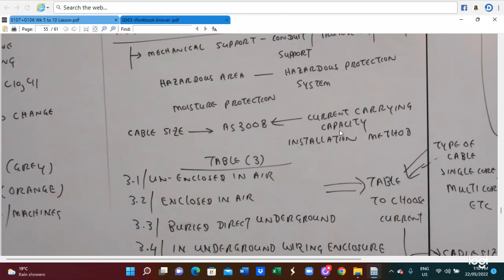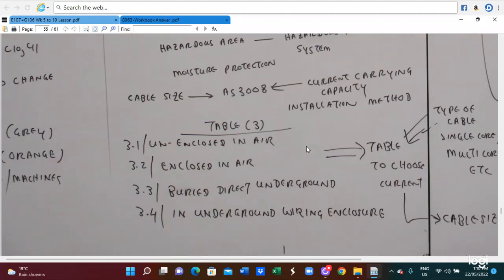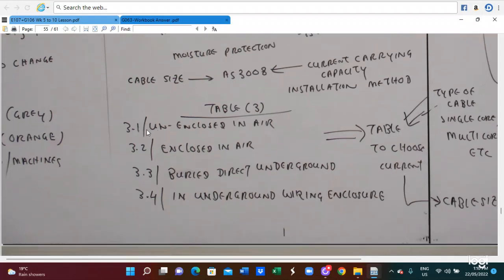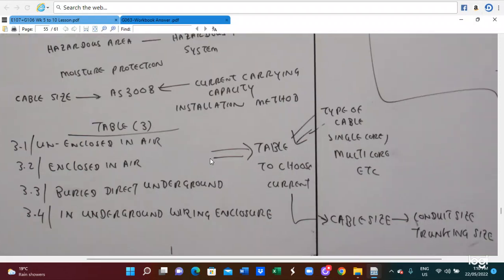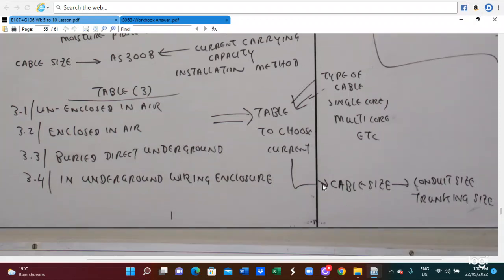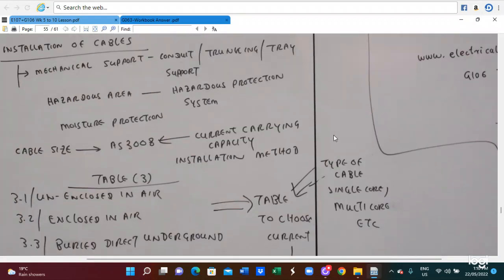This is the current carrying capacity and the installation method. So for cable, 3x1 is un-enclosed in air, 3.2 enclosed in air, 3.3 buried direct underground, and 3.4 is underground wiring enclosure. We have to use an appropriate table to choose. Use a table to choose the type of cable, single core, and the cable size, and the conduit size, and the trunking size need to be selected.